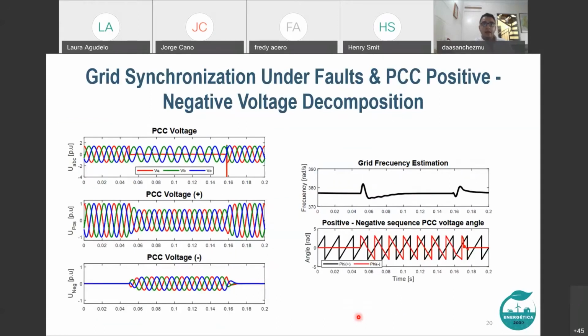So here we have an example of the DSOGI performance. A single phase to ground failure occurs at 50 milliseconds and is cleared at 150 milliseconds. DSOGI decomposes the PCC voltage into positive and negative sequence in a very smooth way. Here is the positive sequence, here is the negative sequence. Also, the DSOGI estimates the grid frequency and the phase angle of the positive and negative sequence PCC voltage.